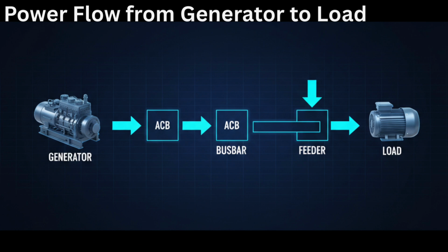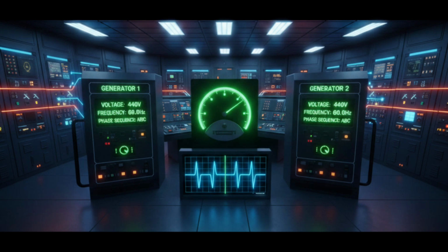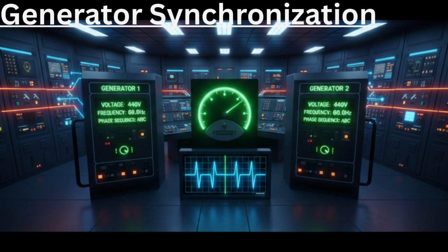If any interruption happens in this path, power supply will be affected. Understanding this flow is essential for troubleshooting and safe operation. Generator synchronization. Before connecting a generator to the busbar, synchronization must be performed. Synchronization means matching four important parameters: voltage, frequency, phase sequence, and phase angle. If these values are not matched properly, heavy circulating current can flow, causing severe damage to the generator.